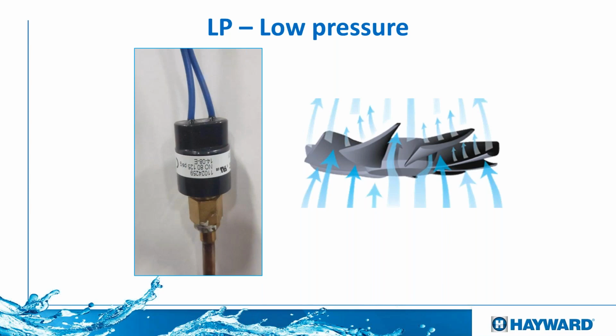If we have LP, low pressure, one of the reasons could be that the compressor comes on, but the fan will not come on. So in that case, let's check voltages, check the capacitor, and maybe check the fan. The fan could be bad or stuck. If everything looks good, then we're going to have to look into refrigerant leaks. Most commonly, this code will be related to low pressure or a leak of refrigerant. But if you have a fan that is not working properly, then we can start that way before we jump into looking for leaks and the whole nine yards.